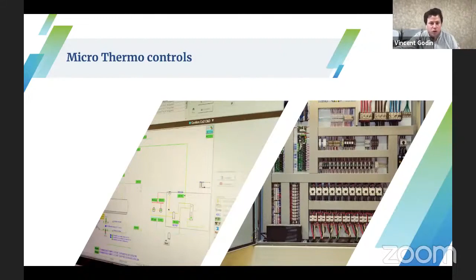So I talked a little bit about it earlier. All of our facility includes heat recovery from the racks. So we get the heat out of the CO2. We inject it into a glycol network that will do the heating of the radiant floors. It will do the heating of the under slab in the freezer. It will also do the defrost on the evaporators in the blast freezer, and it will also do the defrost of the coils in the IQF tunnel.